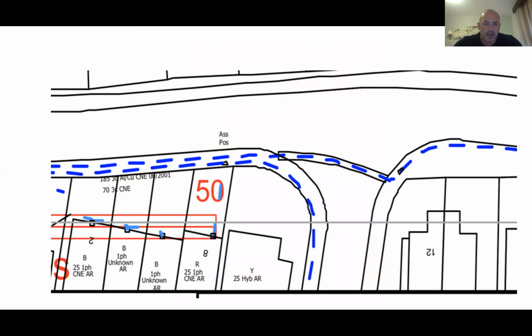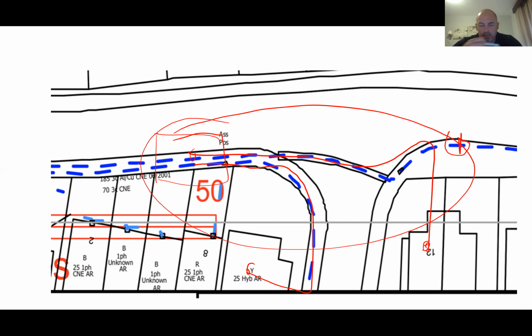So just one last one again, Western Power. You're probably going to get the idea I'm going with this again. Very similar, 2 LVs, passive modes finds 1. How do we find them? We can hook up here to trace the top one. We can hook up here to trace that one. We could even, again, find on power and induce. There's multiple ways of doing it, but this is information from the plan that's helping us locate when there's more than one.